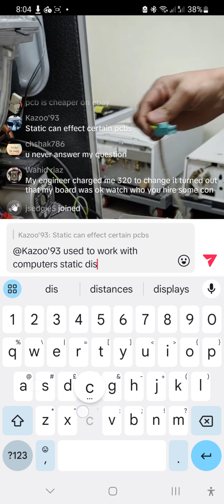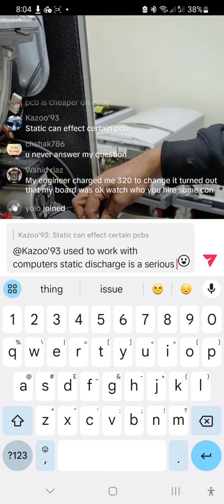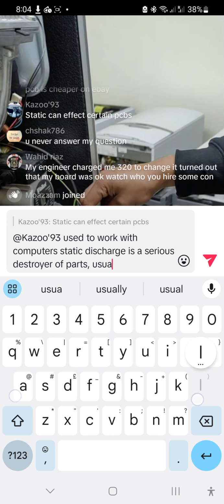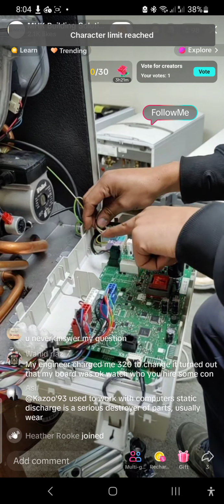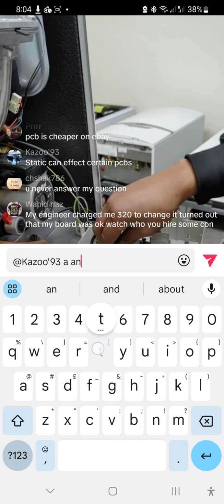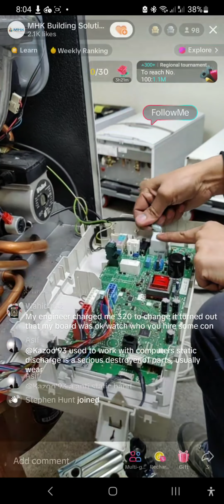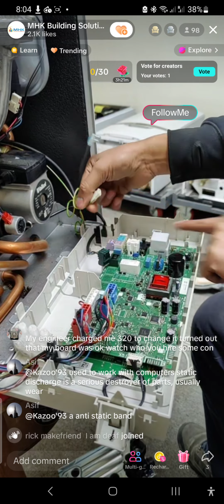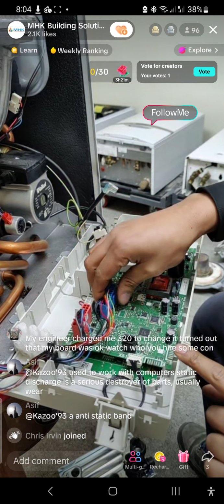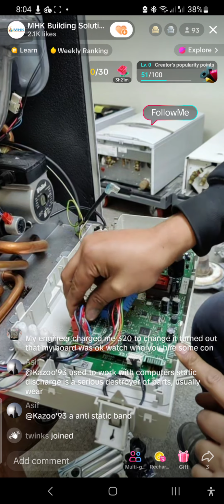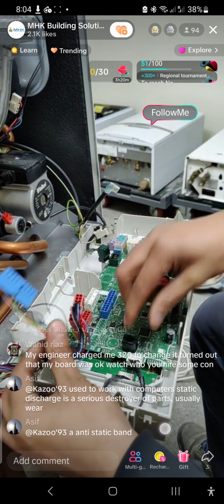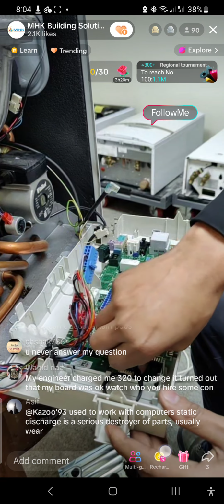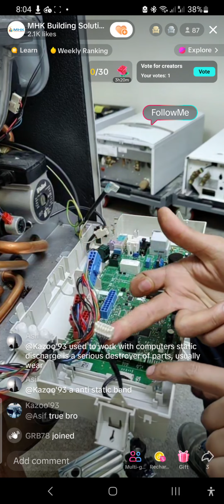So once you've done all of that, you want to make sure that all the connectors are removed. This connector is the main connector that was in here, so we remove this connector. Normally you will have the main supply cable coming from here. Once this connector is removed, then that's out of the way. Pump connection removed, ignition cable removed, earth cable, earth connector removed. These two connectors on the PCB, the red and the blue one, removed. And then the last connector to remove is this white connector that's for the display screen at the bottom.